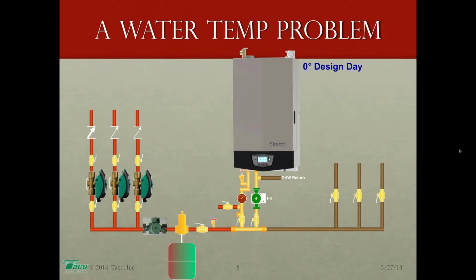Okay. Can you give that GPM formula again? Sure can, John. GPM equals BTUH divided by delta T times 500. And what is the maximum BTUH capacity of the boiler for these pipe sizes and at what delta T? Dan, that's the million dollar question, and to find that answer, I would recommend looking at the specification sheet for each manufacturer. They will give you the pipe sizing and flow rates through the boiler at specific delta Ts for each model, and then you can select which one you need for that application. I hope that answers your question.